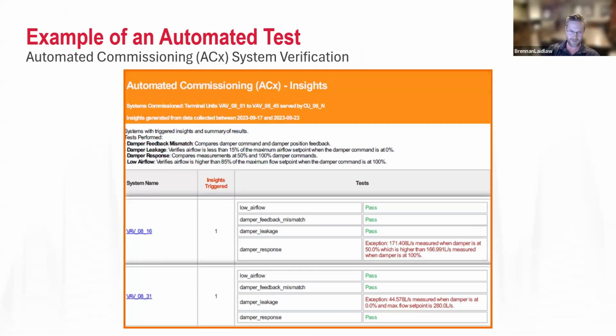The next one was an example of a low damper leakage. They set it to 0%, but it's getting 44 liters per second of airflow. So something's not right. It's not mounted properly. The seals are broken. But it's a good example for the use of automated testing.